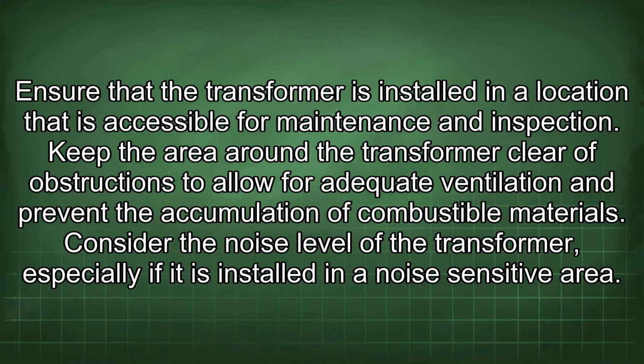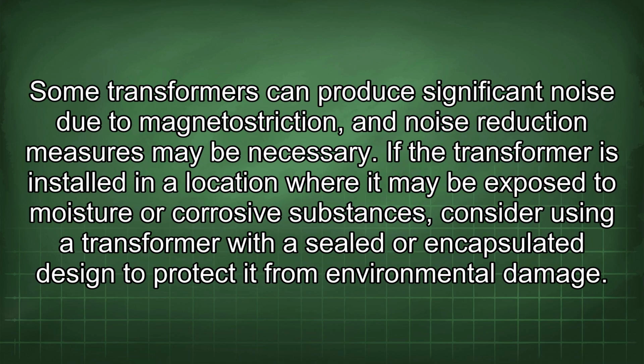Consider the noise level of the transformer, especially if it is installed in a noise-sensitive area. Some transformers can produce significant noise due to magnetostriction, and noise reduction measures may be necessary. If the transformer is installed in a location where it may be exposed to moisture or corrosive substances, consider using a transformer with a sealed or encapsulated design to protect it from environmental damage.